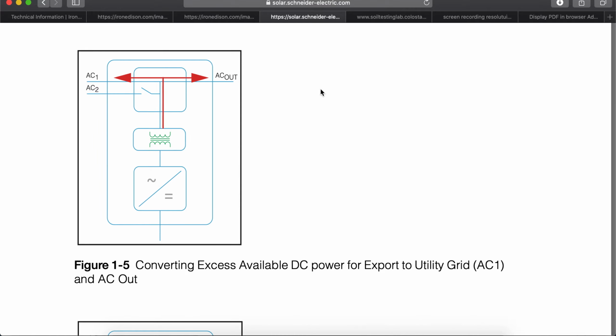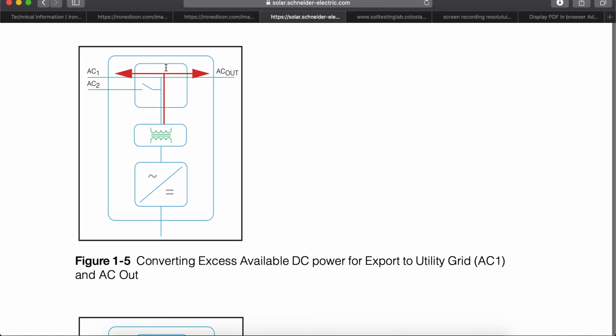Figure 1-5, converting excess available DC power for export to the utility grid, AC1 and AC out. So now we're getting a little bit more technical, but this is exciting. In this diagram, in figure 1-5, we're seeing DC from the battery come up through the inverter. The inverter is now programmed to sell some of that energy back to the grid and provide power to the protected circuit breaker panel. This is the way it works in my house. I sell a little bit back during the daylight hours. I use a programmable time-based window to stop the selling back at about 3 o'clock in the afternoon to make sure that I have plenty of power to make it through the night.